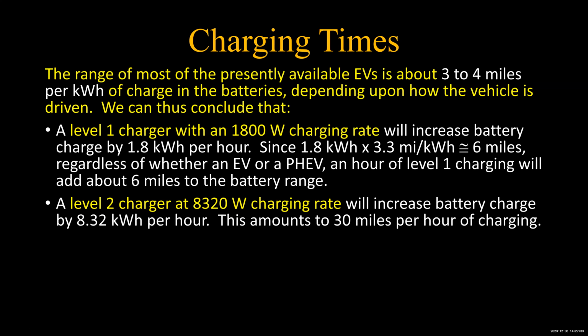So a 50 amp charger in a condominium or any other building, an office building that's served by 120/208, is going to run at about 8,320 watts. And what that does, of course, is increases the battery charge by 8.32 kilowatt hours per hour. And 8.32 times 3.5, we're looking at about 30 miles an hour. All right, so level 2 at 8,320 watts, roughly 30 miles an hour of charging. Charge overnight for 10 hours, 300 miles. So, you know, who drives more than that?